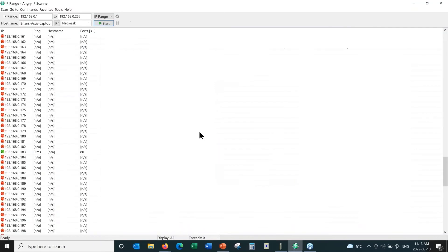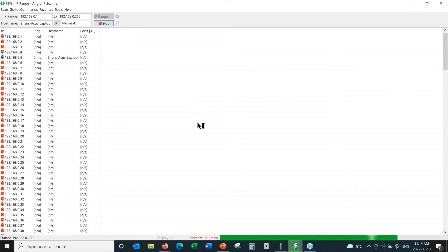If these are brand new radios right out of the box, the IP address is printed on the side label and it's called the setup IP address. These radios have a dip switch that allows you to cycle between setup and run mode. In setup mode, the IP address reverts to the default printed on the side label. I'm going to show you a program called Angry IP Scanner — a very useful program. I've set it up to scan a range of IP addresses and I'm going to hit start.